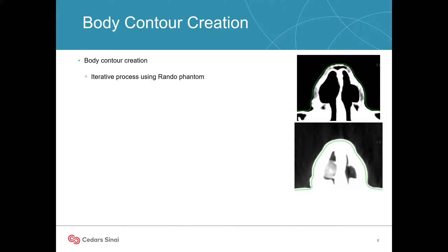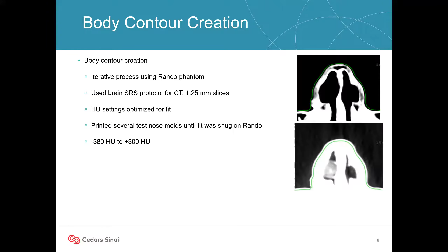And on the right, you can see that by changing your window and level, you can get a very different body surface. So for us, we CT'd our rando phantom with an SRS protocol and 1.25mm slices and wanted to optimize the Hounsfield units. We did print several different applicators and checked them on CT until we found the right fit for the rando phantom. And for us, we found that using our Brain SRS protocol, our Hounsfield window that we used for optimal fit was -380 to +300.